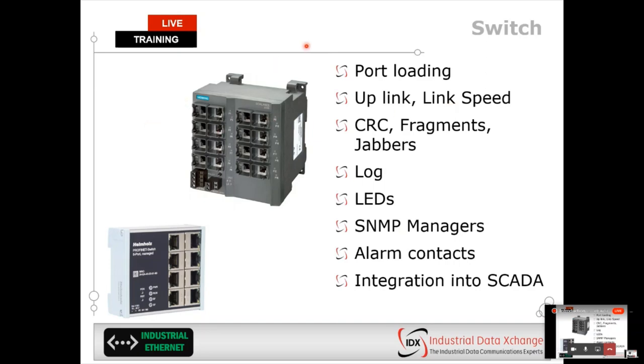Why it's important to know that the link speed is at 10 megabits per second is that it means I'm running a half duplex system. Sometimes that's acceptable; some Ethernet components, like printers, some HMIs, and even some power meters, are designed to run at 10 megabits per second by nature. Switches are intelligent enough to connect 10 megabits per second devices to 100 megabits per second networks — that's called auto-negotiation. But if you've connected a component that should be running at 100 megabits per second, and the statistic in the switch tells you it's at 10, it means you have a problem, probably some sort of cable error that you need to identify and fix. So make sure all your link speeds are running at the speed you expect.